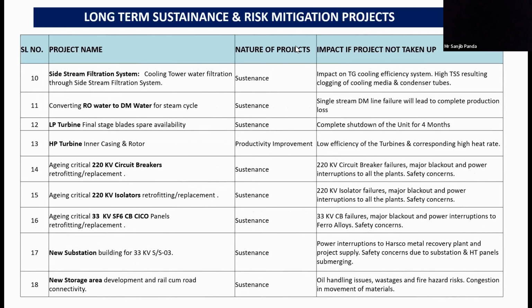I'll quickly go through as we are running out of time. Side stream filtration system. This again is to bring down the TSS in the system and also keep the cooling water system and the condenser tube clean, fills clean, so that we get the temperature, the delta T across the condenser, as well as the vacuum as per the design.